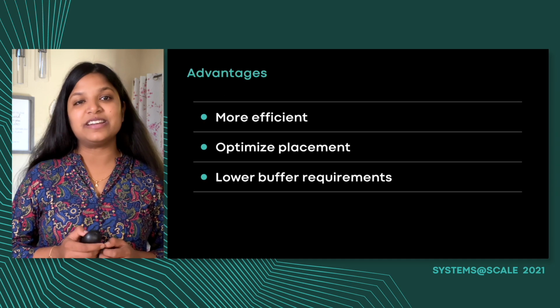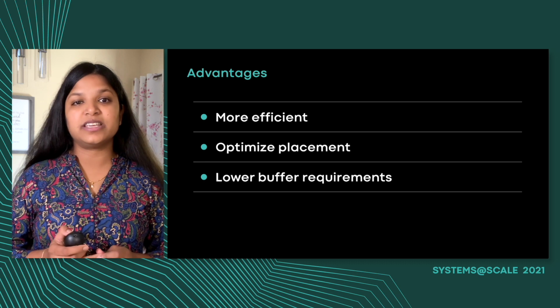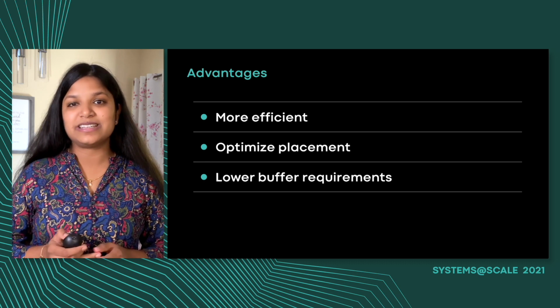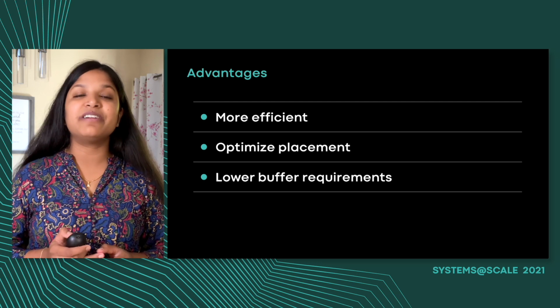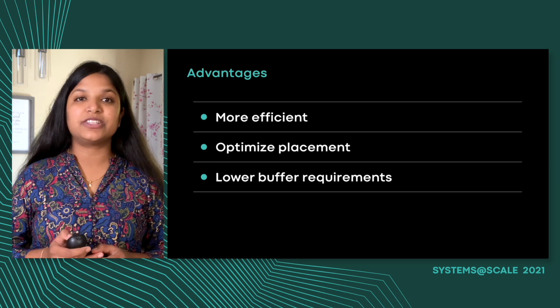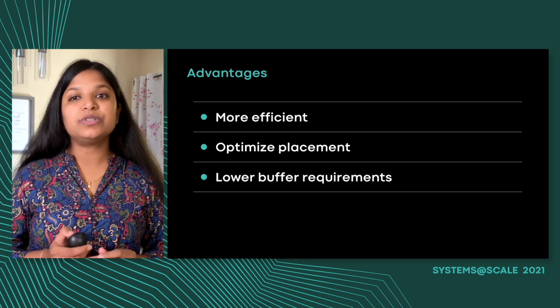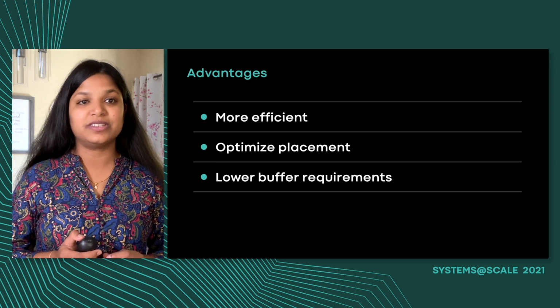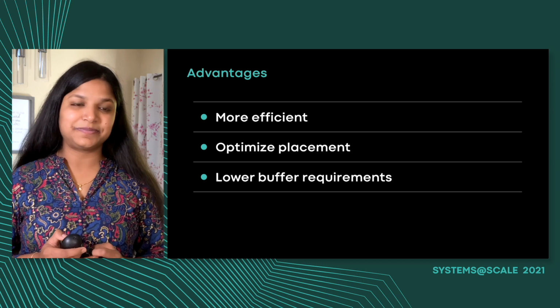Let's look at the advantages with this approach. The reason this is very important for us is we have buffers in our data centers where we have extra server capacity to tolerate any one of the power devices' outage. Now, with the dual powered architecture, if an MSB was experiencing an outage, we would lose an entire row of critical services and we would only have one row of buffer capacity.